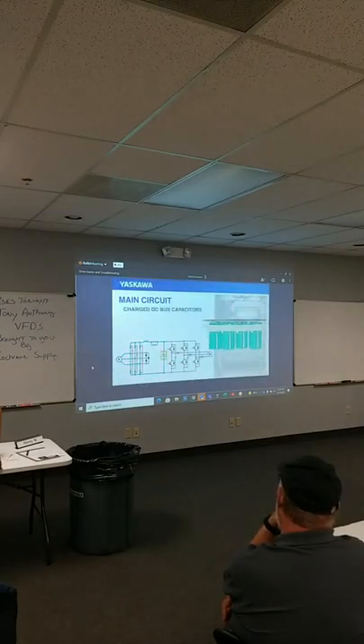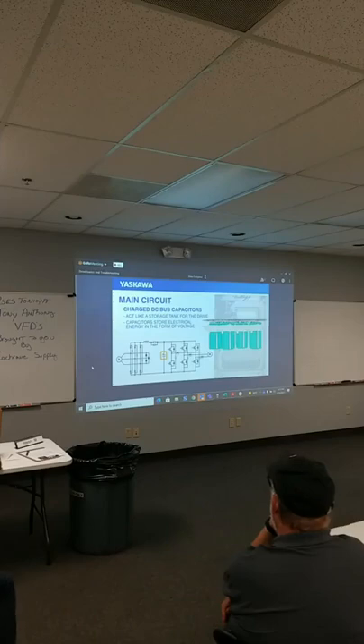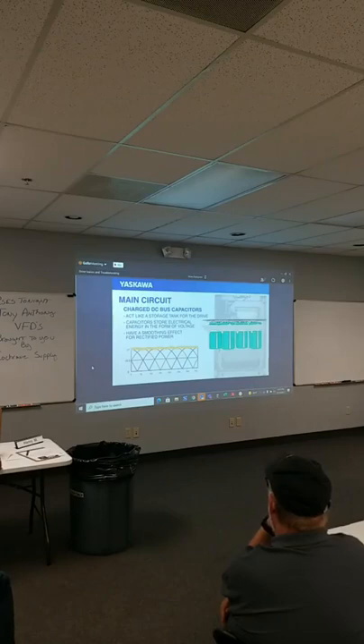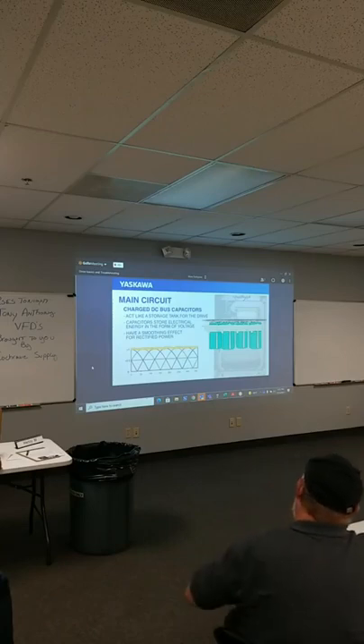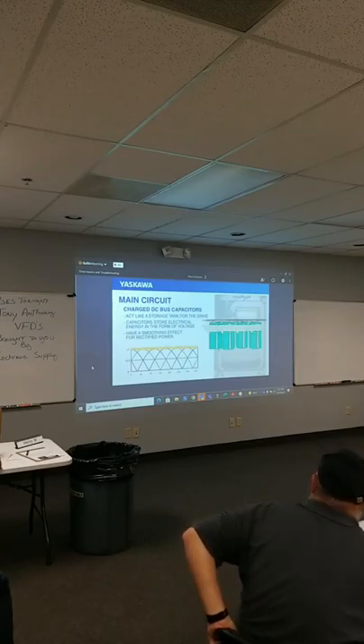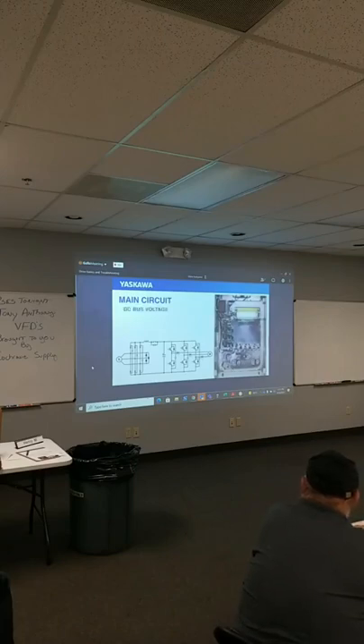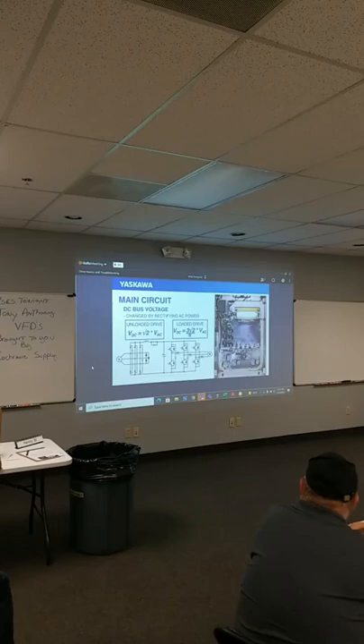Once the DC bus capacitors are charged, they act like a storage tank for the drive. The capacitor stores voltage for the system. These capacitors also have a smoothing effect for rectifying power. This smoothing reduces the peaks and valleys of the three-phase incoming power that has been rectified. This reduction in ripple helps reduce the wear on the system as a whole. It's also important to note that the voltage level in the drive is now changed by rectifying AC power. The new DC bus voltage can be calculated using this formula: VDC equals the square root of 2 times the voltage of the incoming AC.